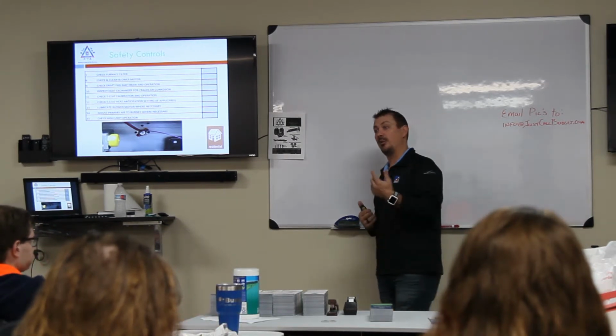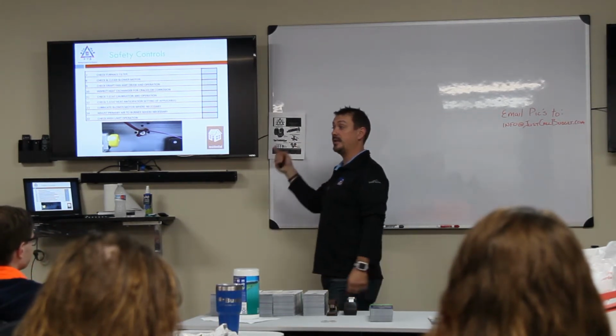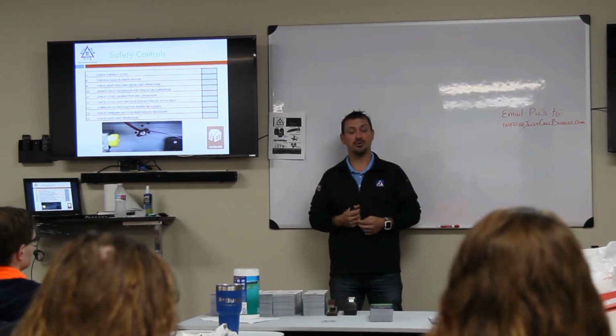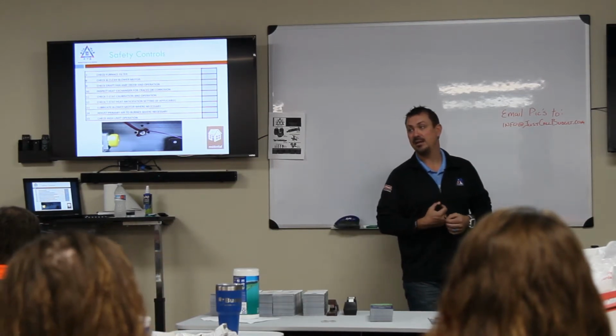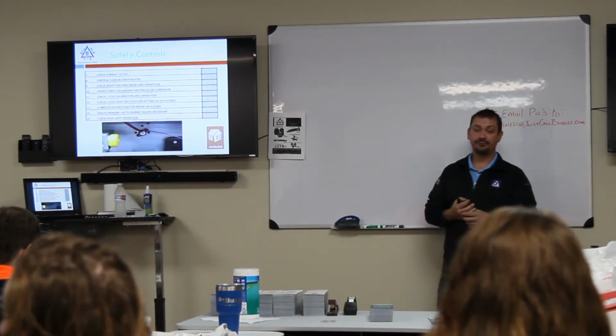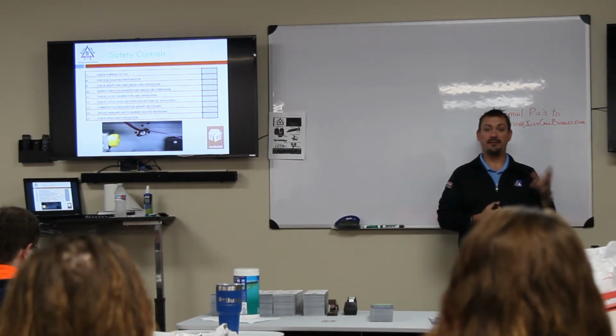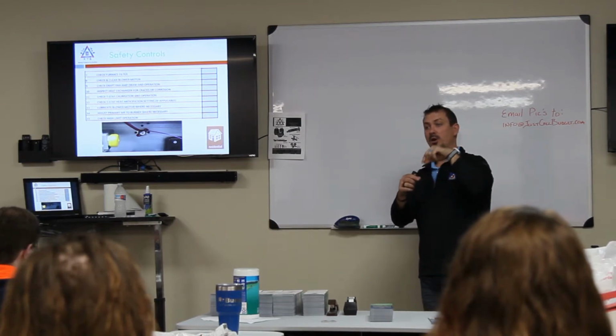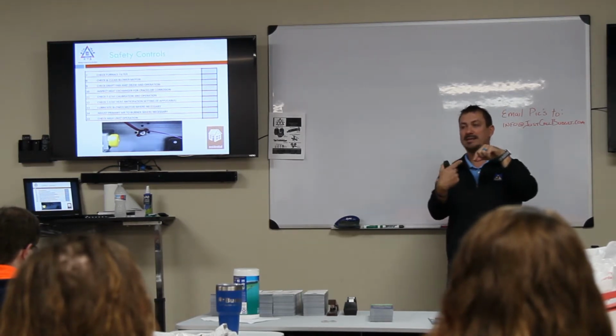Okay? And moisture will get inside the pressure switch because of a couple of different reasons, and one of them is gas pressure. That's one of the leading reasons why it will get in there. If the gas pressure is running a little bit low, the flue gases will condensate and cause moisture to get inside the inducer and then that tube, getting that diaphragm wet, or there's actually a little tiny hole where that hose goes onto that pressure switch. If you look on the back side of there, there's a little tiny weep hole on there.